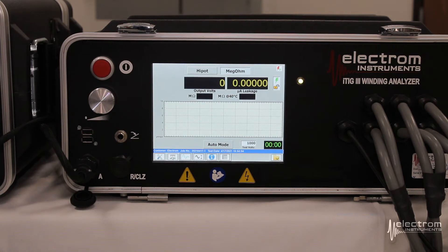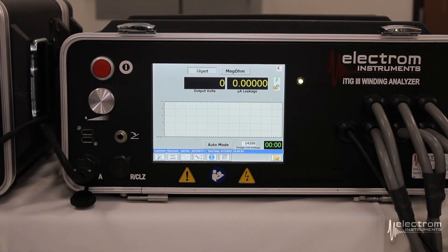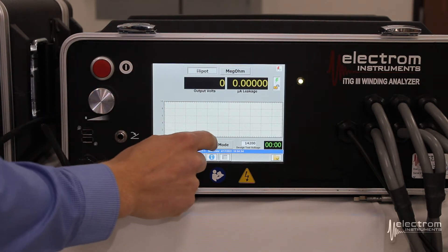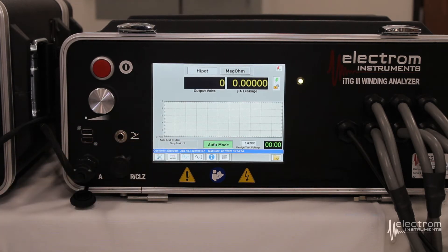Moving one tab over, we get to our mega ohm and hipot screen. Again, we recommend using the itig 3 for the mega ohm measurement because of the increase in resolution and accuracy. So we will move on to the hipot test. Click auto mode — it tells you in the bottom left corner which test profile has been selected. We selected the 5-point step test.